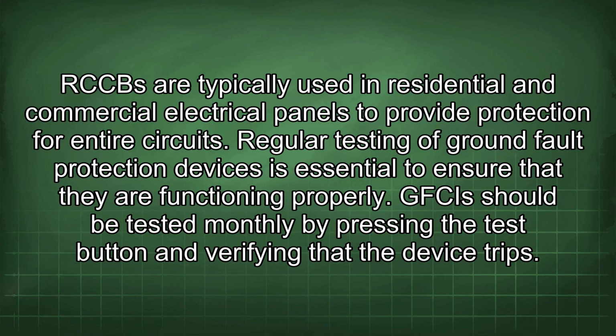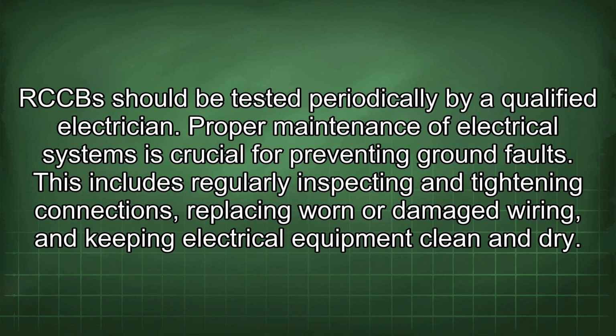GFCIs should be tested monthly by pressing the test button and verifying that the device trips. RCCBs should be tested periodically by a qualified electrician. Proper maintenance of electrical systems is crucial for preventing ground faults. This includes regularly inspecting and tightening connections, replacing worn or damaged wiring, and keeping electrical equipment clean and dry.